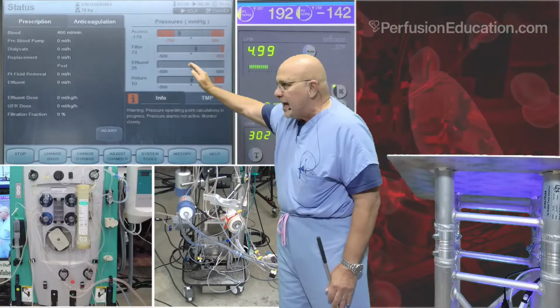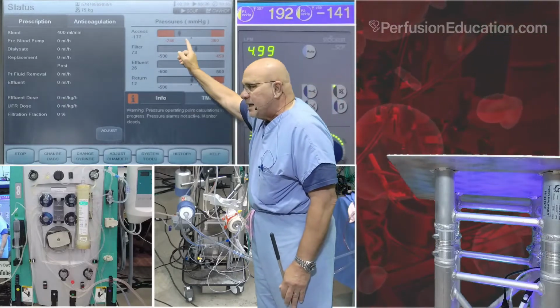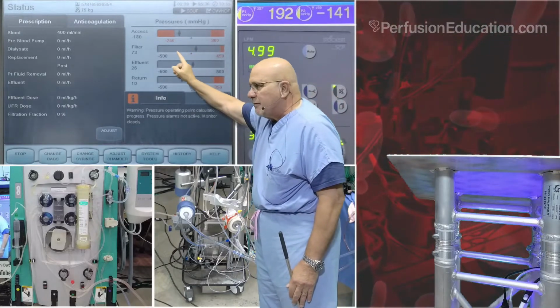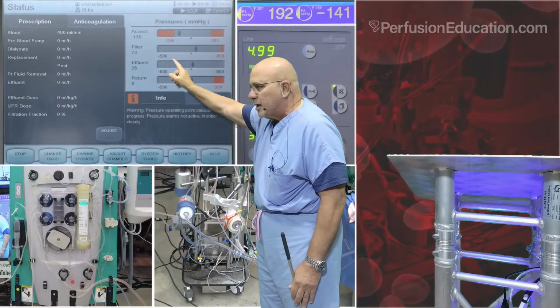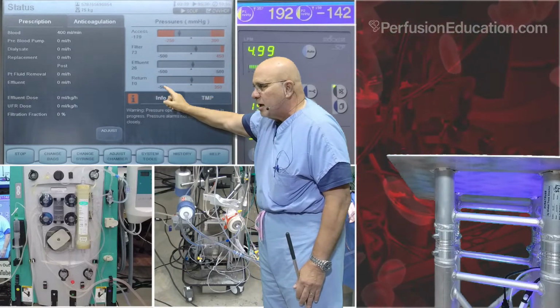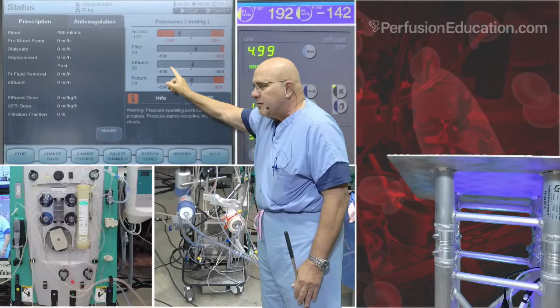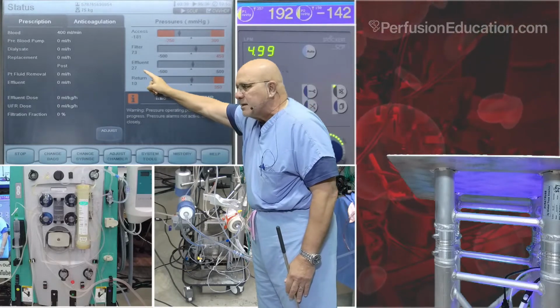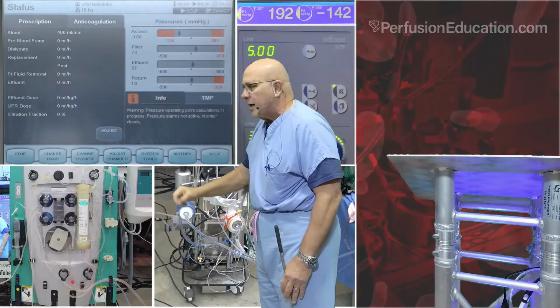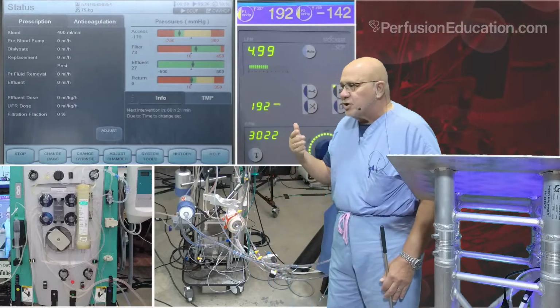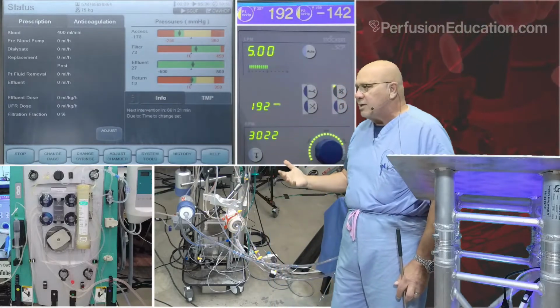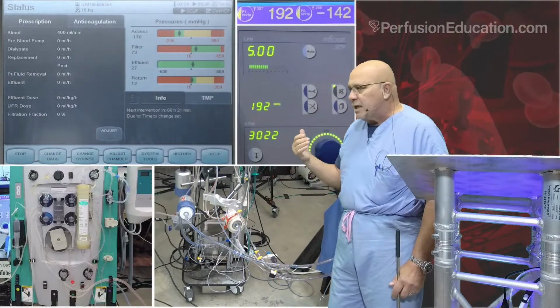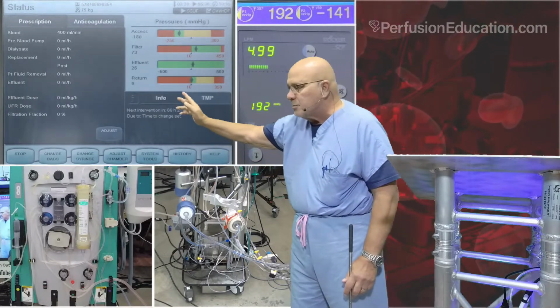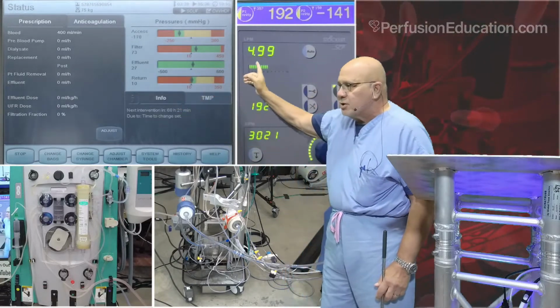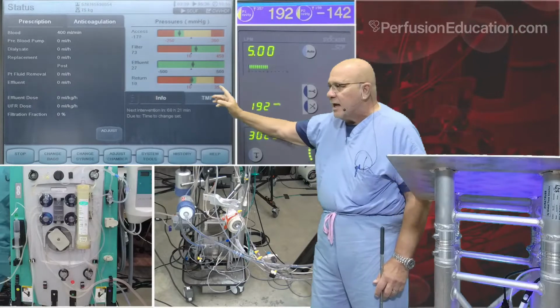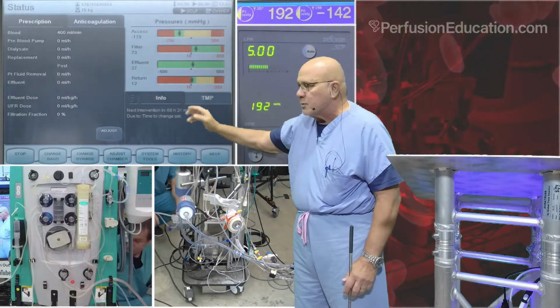You have an access pressure now of 177. You have a filter pressure of 73, a return pressure of 10, but an effluent pressure which is now positive in the 27 range. So to show you how much the circuit will influence your CRRT machine, go down to 4.5 again, and let's watch and see what happens with these numbers.